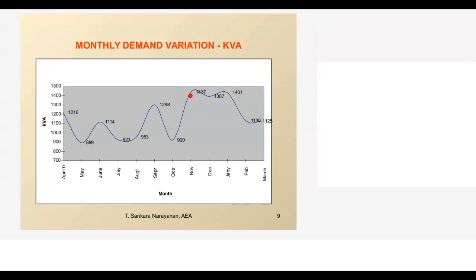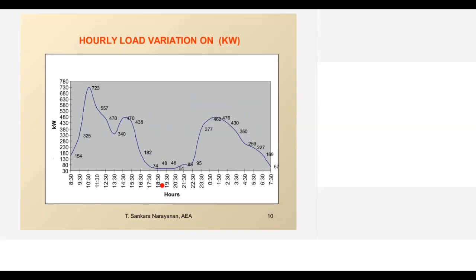So once we have gone through the monthly demand variation, we have plotted the daily variation. See, the daily variation is still different. It starts in the morning at 8:30, goes to a maximum up to 10:30, then again certain changes. In the evening peak hours, they don't run the major equipment. Then again at night it is going. Then after 2:30 or 3:30, it is again dropping. This type of load curve clearly indicates the plant is amenable to certain load management.